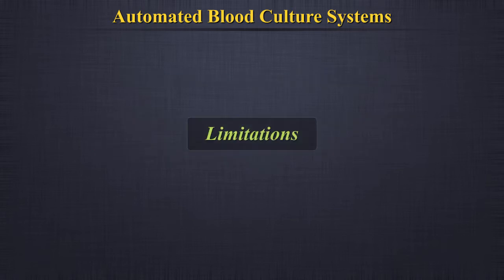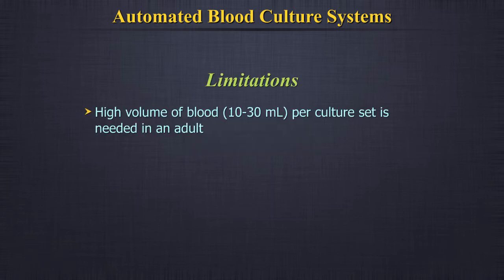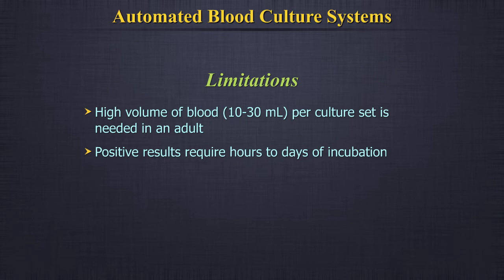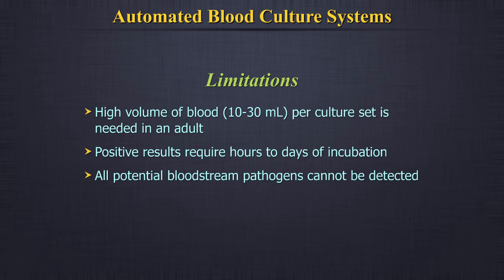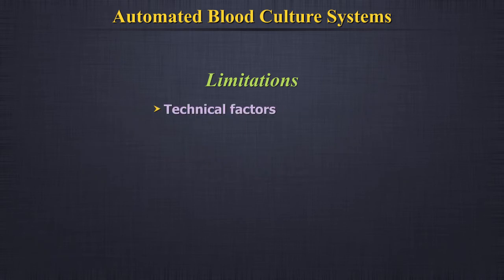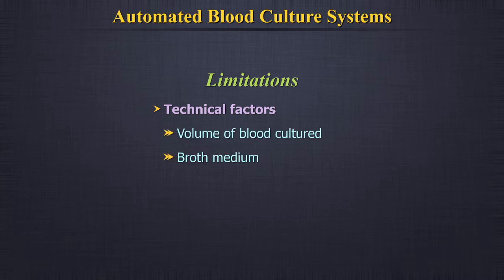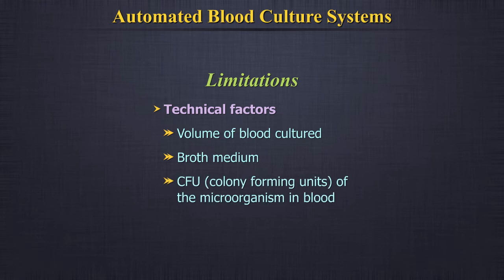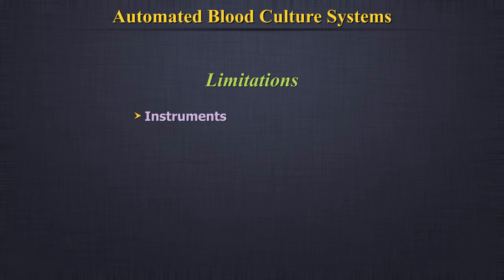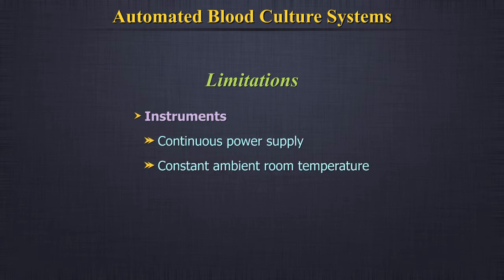Limitations. Automated blood culture systems currently represent the gold standard for diagnosis of septicemia; nonetheless, they have the following limitations. A very high volume of blood — about 10 to 30 millilitres per culture set — is needed in an adult. Positive results require hours to days of incubation. Not all potential bloodstream pathogens can be detected. Many technical factors can cause variability in sensitivity, most importantly the volume of blood cultured, the broth medium used, and the initial colony-forming units of the microorganism in the blood. These instruments also require continuous power supply and constant ambient room temperature.